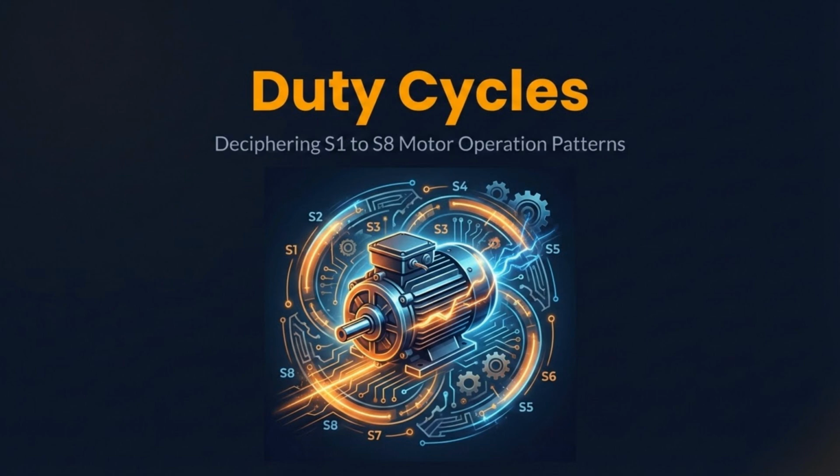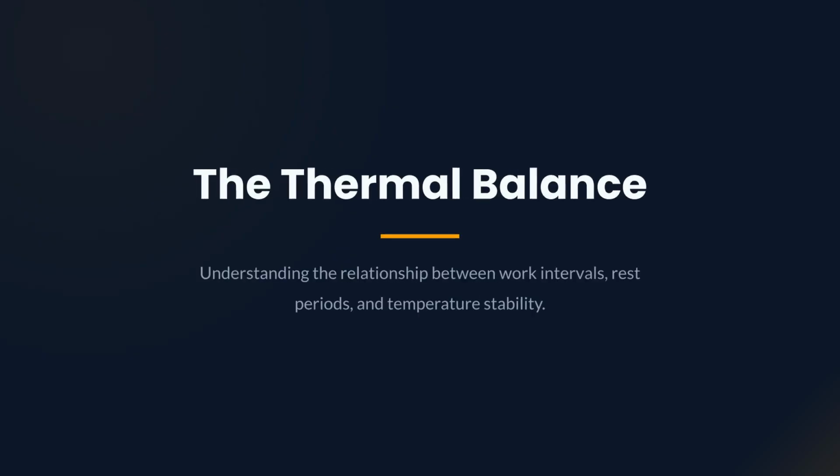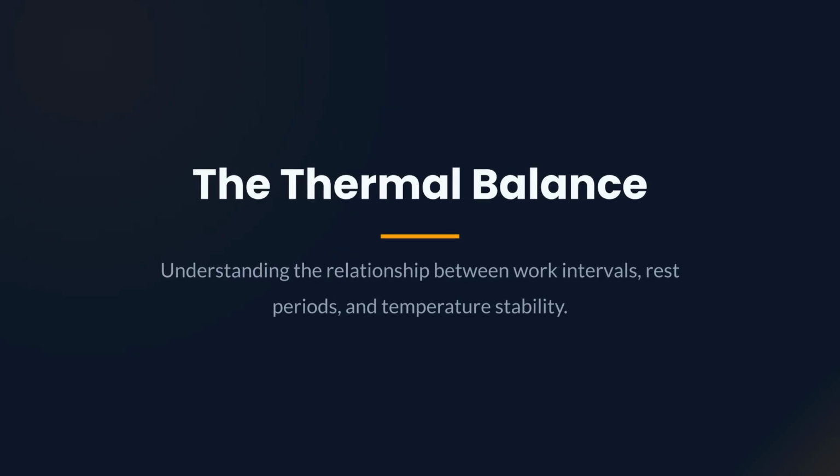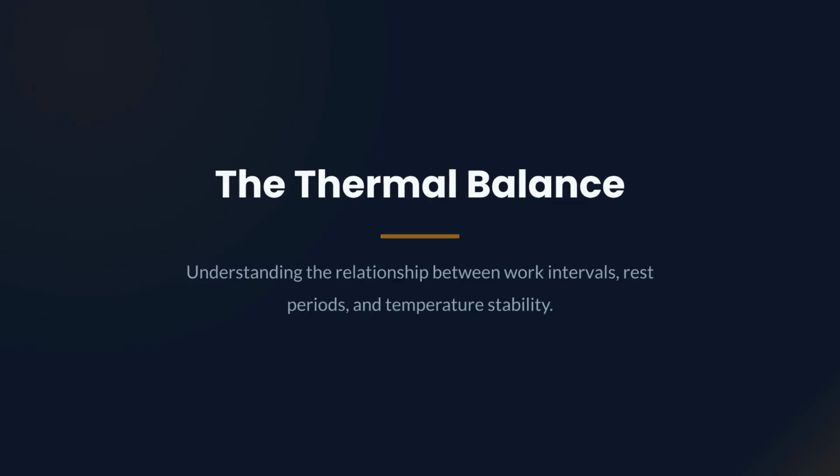Welcome to this video on duty cycles, where we will decipher the S1 through S8 motor operation patterns. Understanding these patterns is key to selecting the correct motor for your application. At the core of duty cycles is the thermal balance. We must understand the relationship between work intervals, rest periods, and temperature stability to prevent overheating and premature failure.